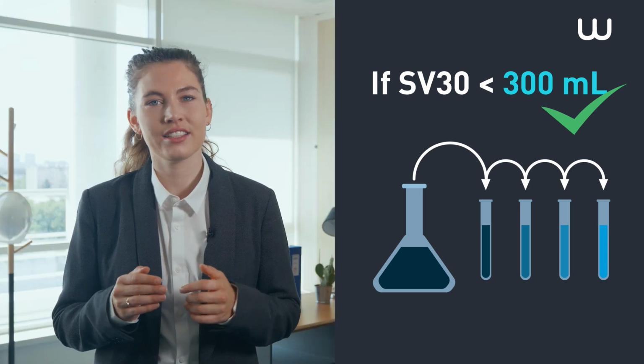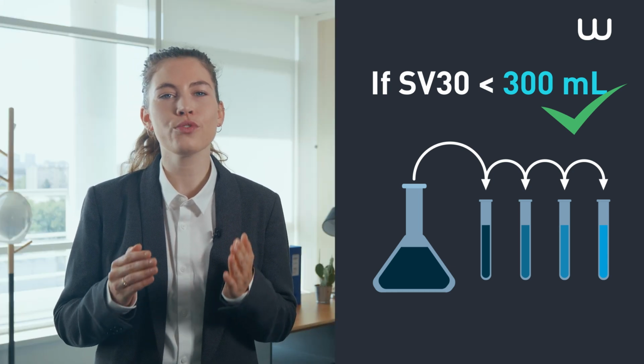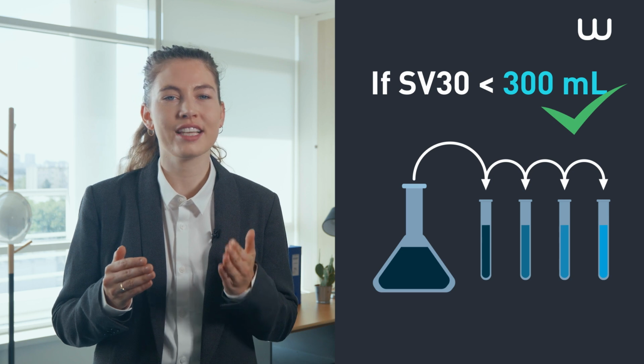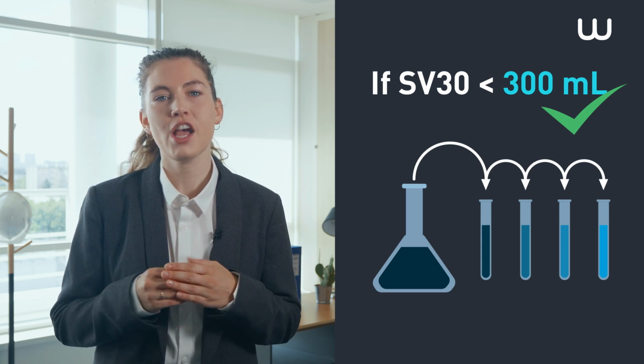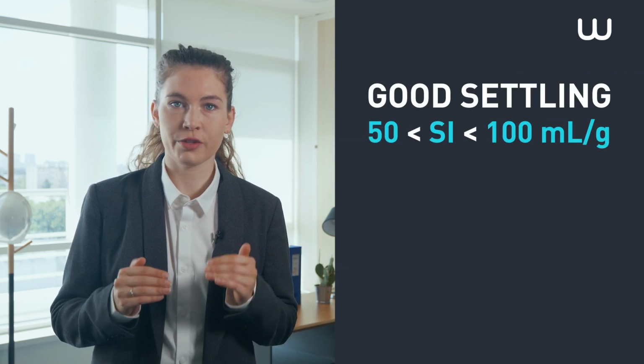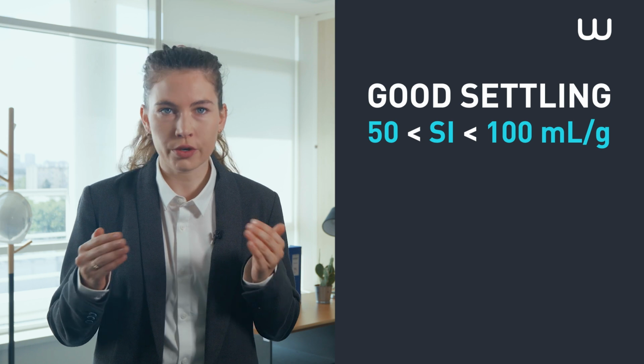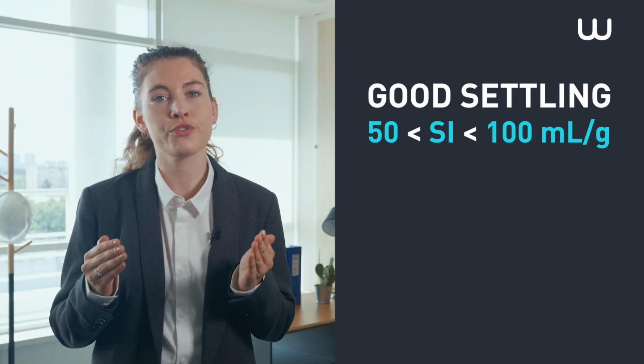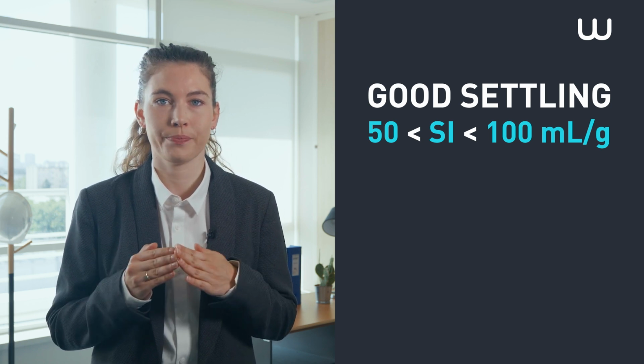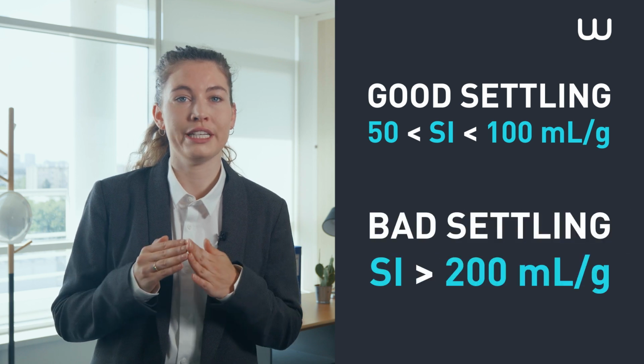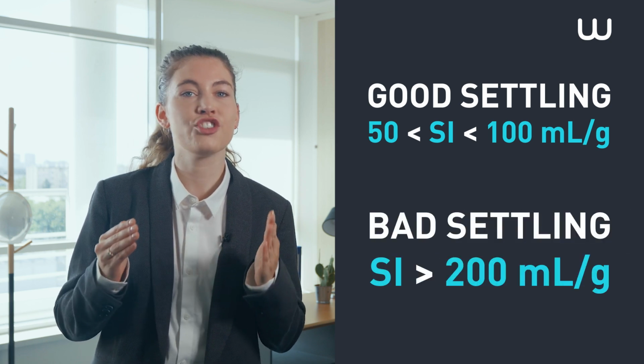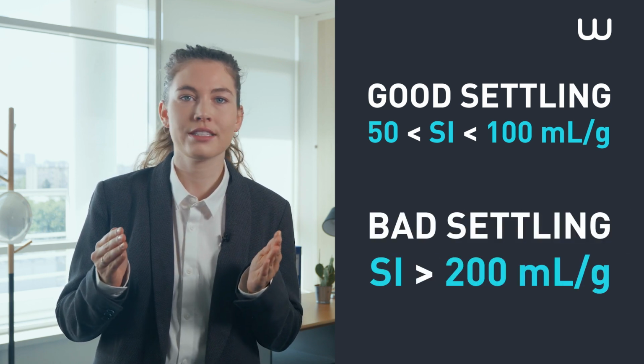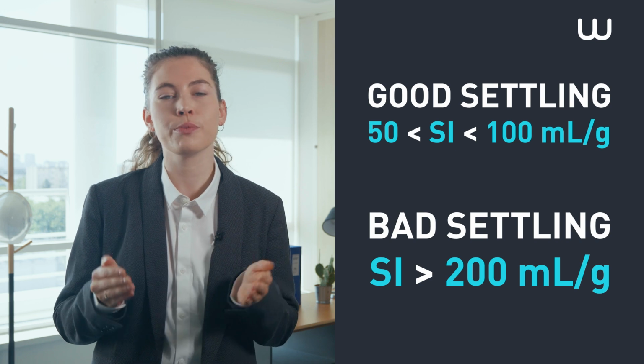The SI is the volume occupied by 1 gram of sludge following settling for 30 minutes. The lower the SI, the better the settling, on the order of 50 to 100 milliliters per gram. Beyond 200 milliliters per gram, sludge is generally filamentous, settles badly, and poses a problem.